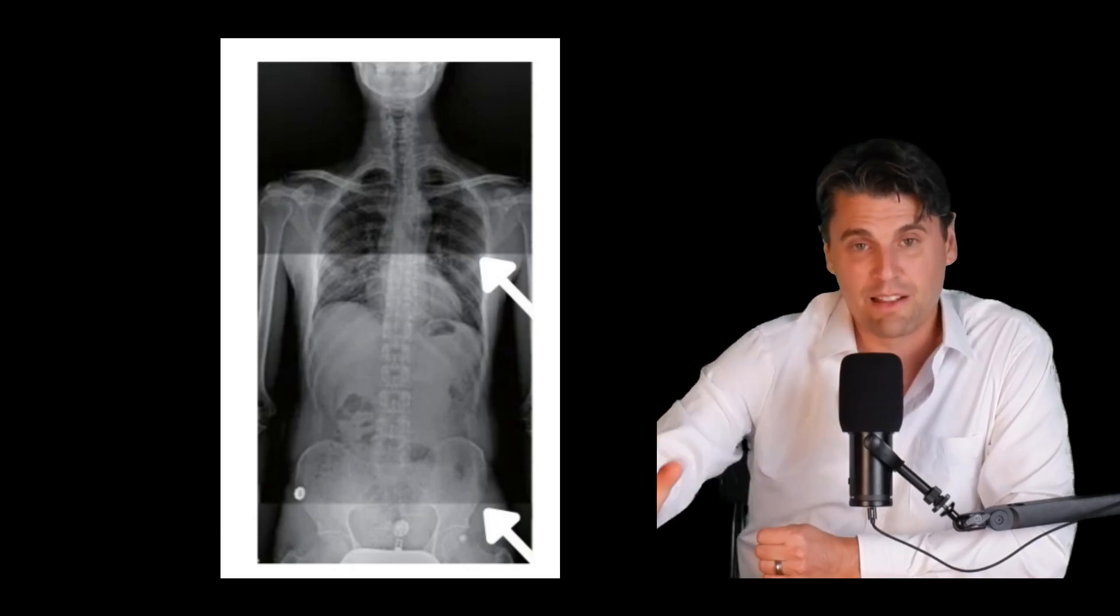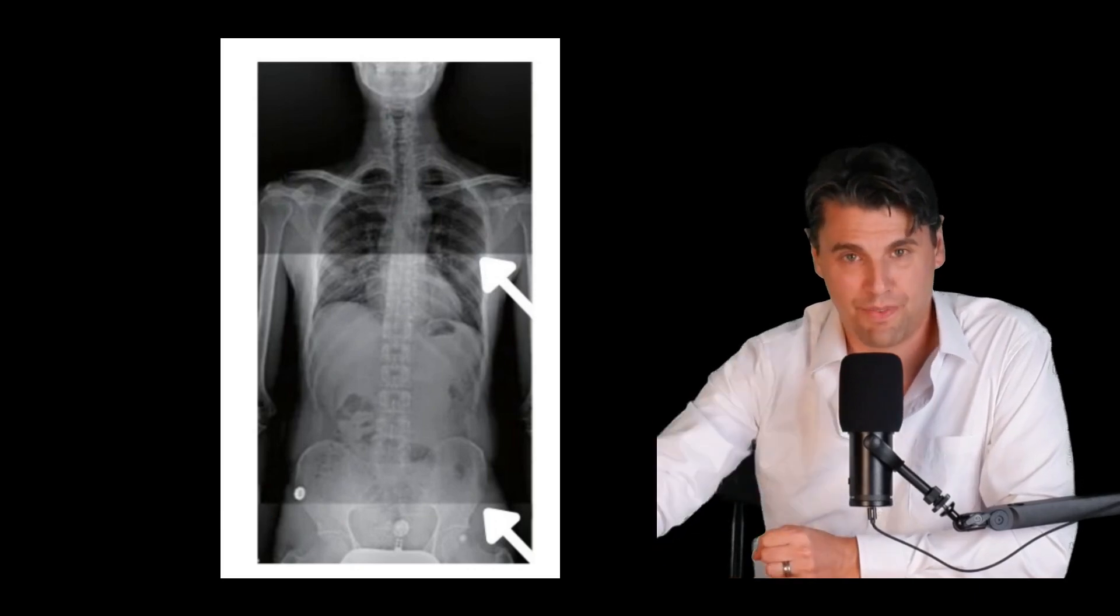There's actually software now to try and reduce those effects. Other artifacts you could have are on a CR system you could have a double exposure where you expose the plate once and then without reading out the plate or without actually erasing the plate you could get what's called a double exposure.